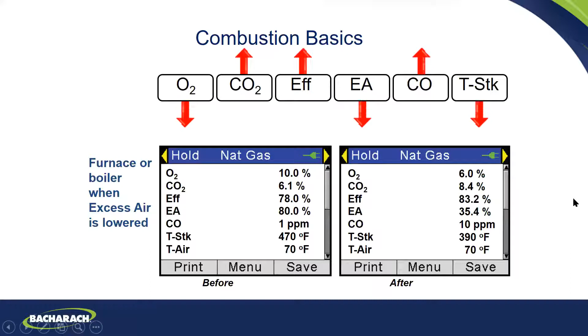So on my personal analyzer, I like to set it up where I have oxygen, then I have CO, then I have stack temperature, and then I look at efficiency. And those four parameters, oxygen, CO, stack temperature, and efficiency, really give me what I need to know here. Now we brought this down to here. Okay, we're still within the sweet spot. If I kept on going, it would probably start making a lot of carbon monoxide.